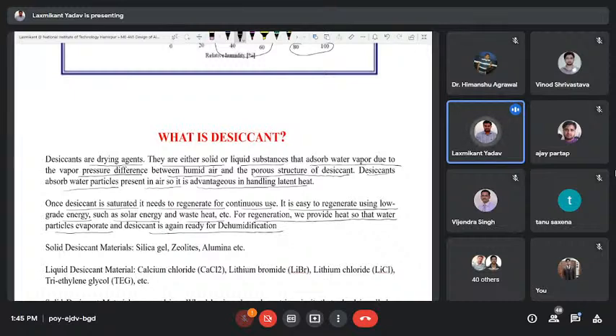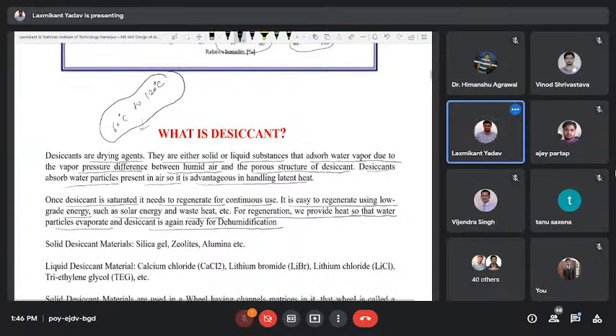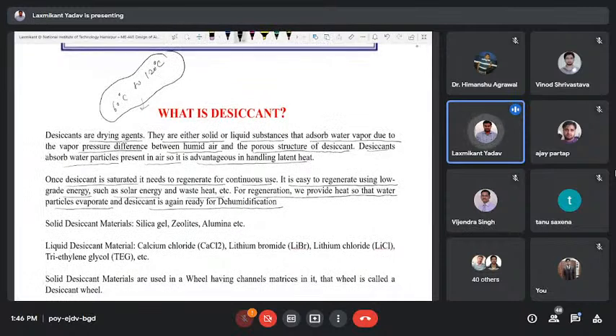Once the desiccant is saturated, it requires regeneration. For regeneration, we basically use solar energy or waste heat. The regeneration temperature is around 60 degrees Celsius to 120 degrees Celsius, depending upon the type of desiccant. This is a low temperature that we can easily achieve with solar collectors. The different solid desiccant materials that are commercially used are silica gel, zeolites, alumina, etc.